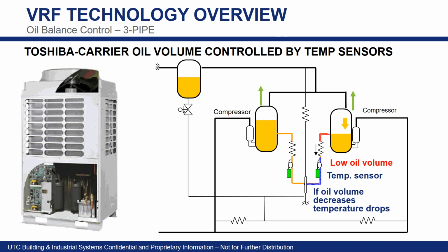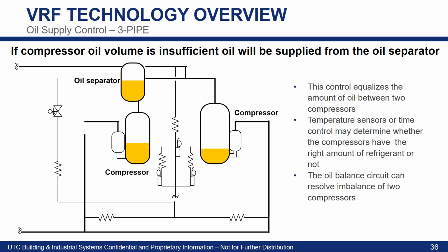Opening up solenoid valves, whatnot. You can see right here, big bold black letters. If compressor oil is insufficient, oil will be supplied from the oil separator. The control equalizes the amount of oil between two compressors. Temperature sensors or time control may determine whether the compressors have the right amount of refrigerant or not. The oil balance circuit can resolve imbalance of two compressors.